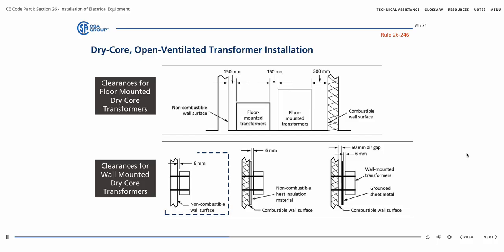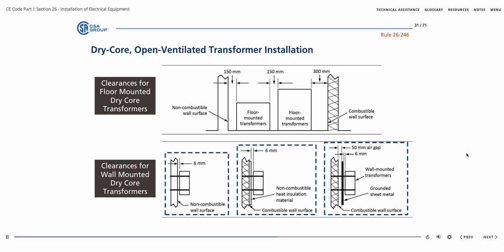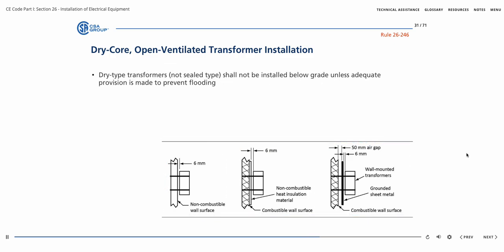made of A. non-combustible material, B. combustible material adequately protected by non-combustible heat-insulating material other than sheet metal, or C. combustible material shielded by grounded sheet metal with an airspace of not less than 50 millimeters between the sheet metal and the combustible material. Dry-type transformers not of the sealed type shall not be installed below grade level unless adequate provision is made to prevent flooding.